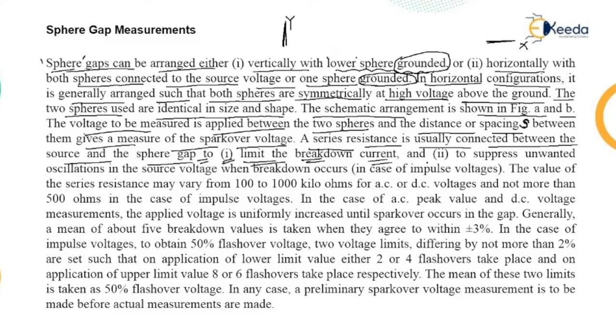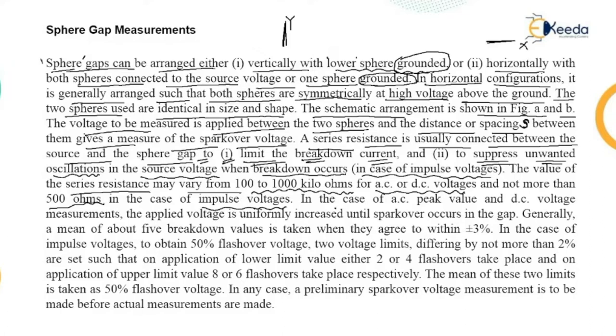A series resistance is generally connected between the source and the sphere gap. The purpose is to limit the breakdown current, as current will definitely occur, as well as to suppress unwanted oscillations — resistance is the best electrical element to suppress oscillations in the source voltage when breakdown occurs. In case of impulse voltages, the value of the series resistance should not exceed 500 ohms.